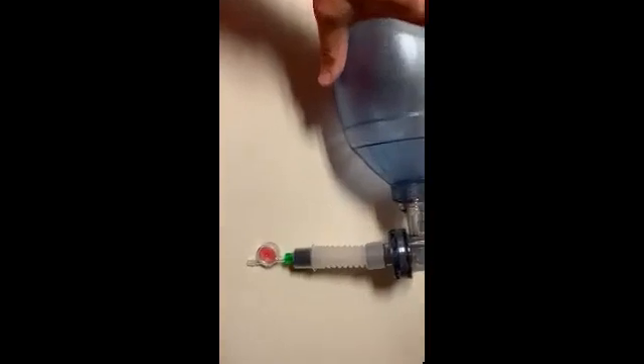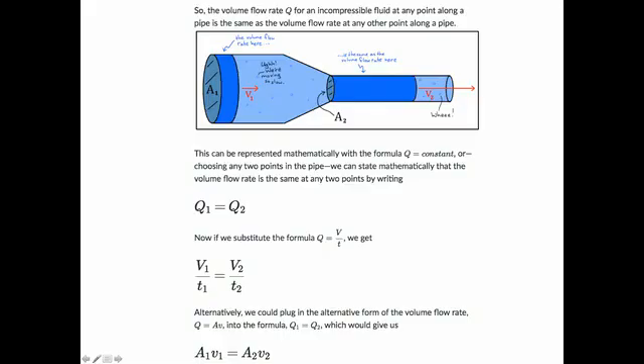Here the pinwheel is attached to the Ambu bag. If diameters A1 and A2 are known, it can be plugged into this equation to calculate volume flow.